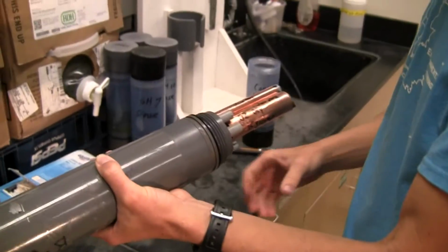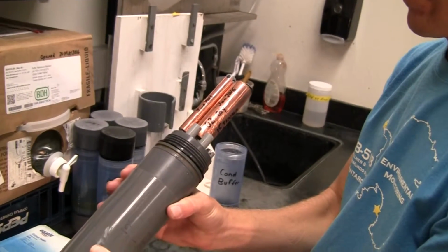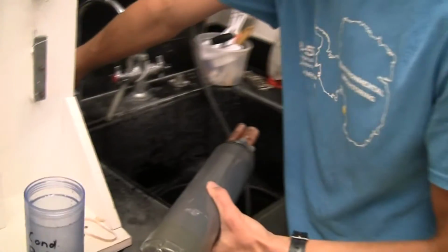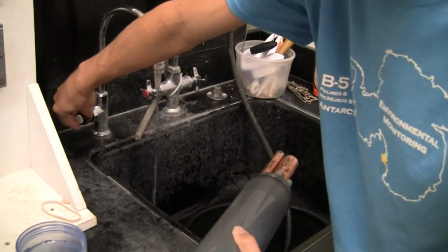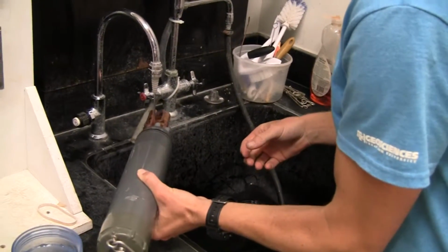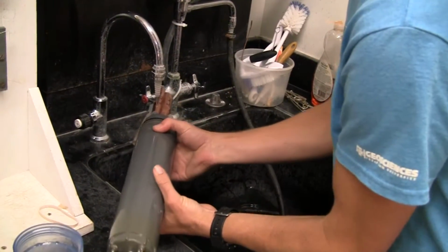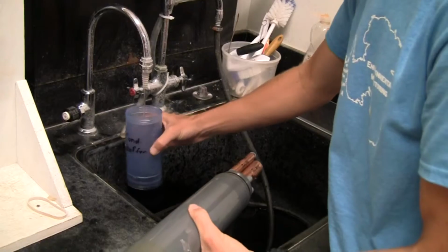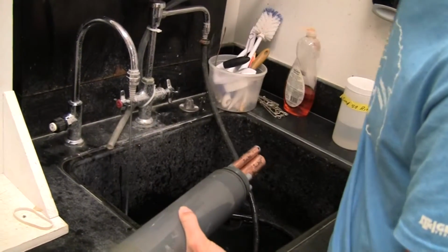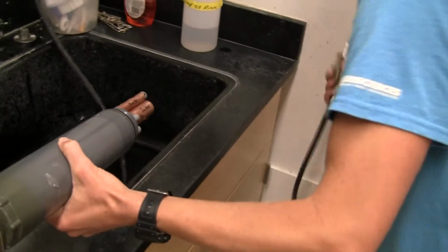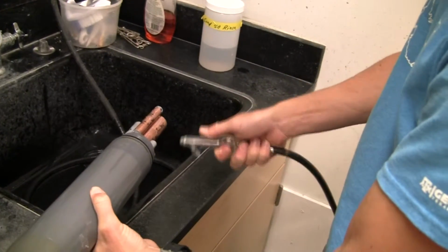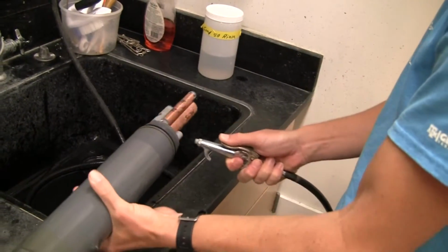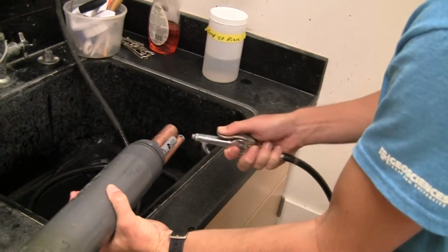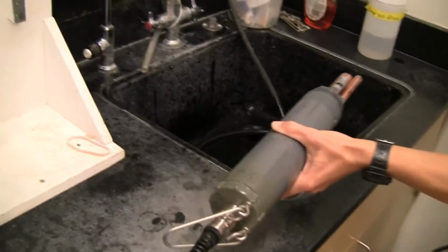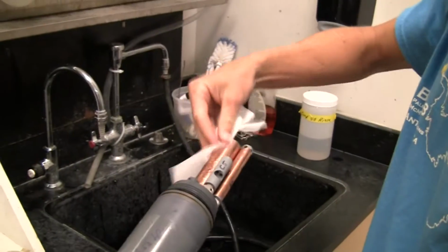Okay. Now the Sonde unit is dirty because it's been in conductivity, so we need to rinse it off with our DI water. So we rinse with DI, and just as we did before, we blow it with the compressed air. And rinse and clean the conductivity jar and place above to dry. So we get our compressed air and we fully clean the sensor again. And wipe dry with the Kimtech wipe.